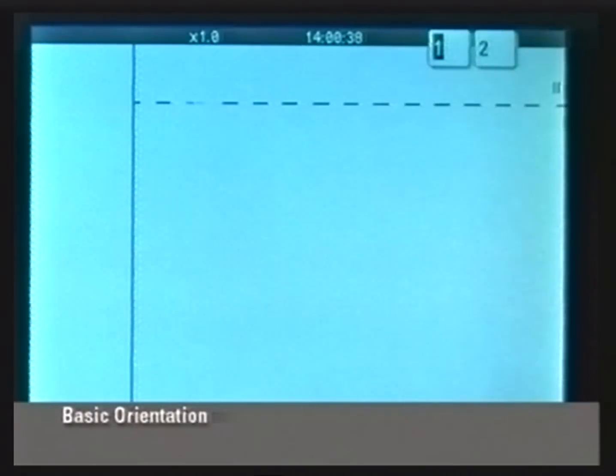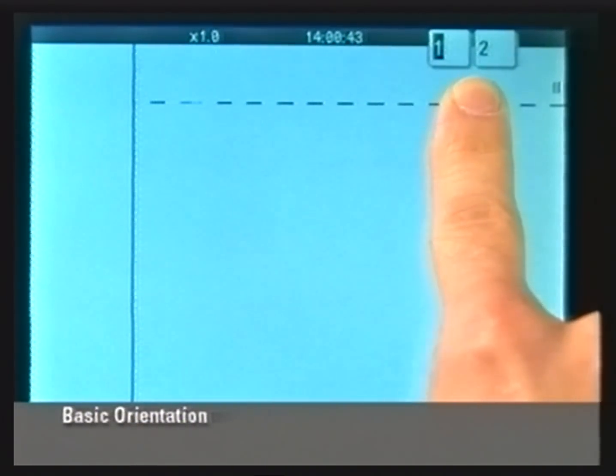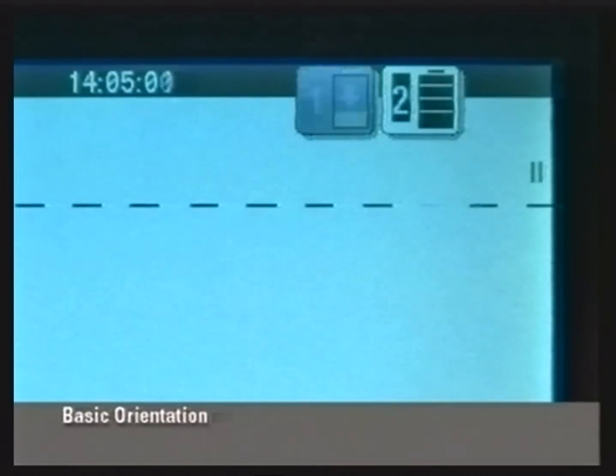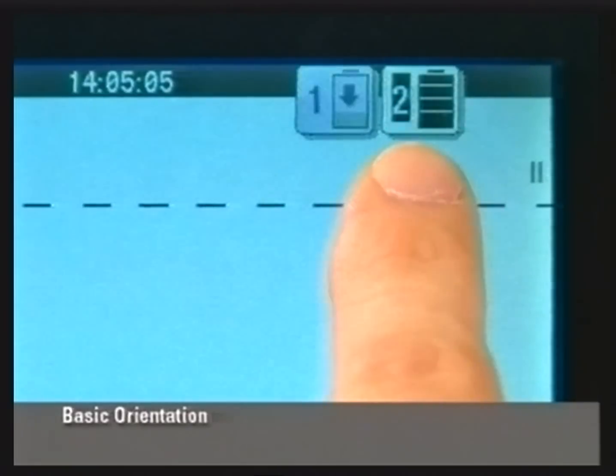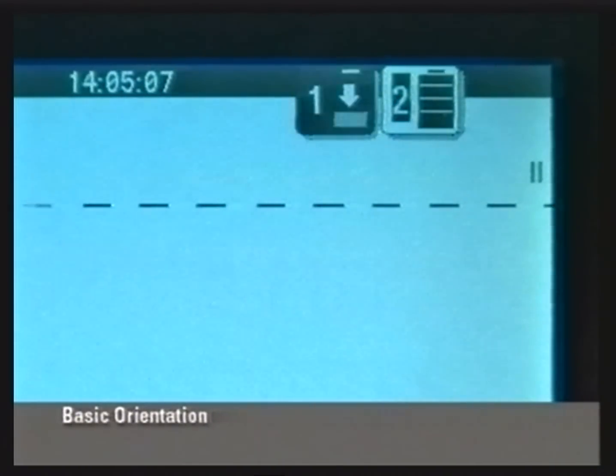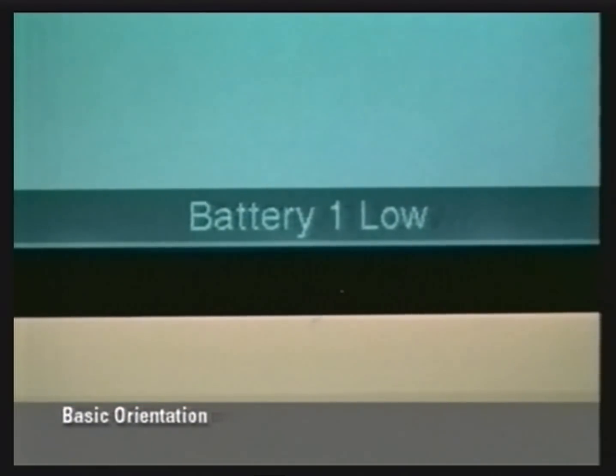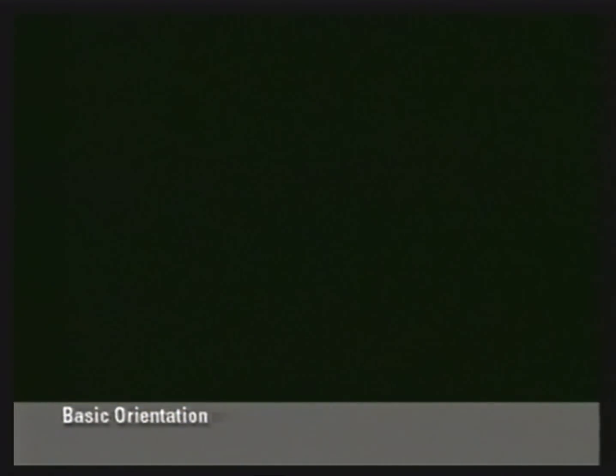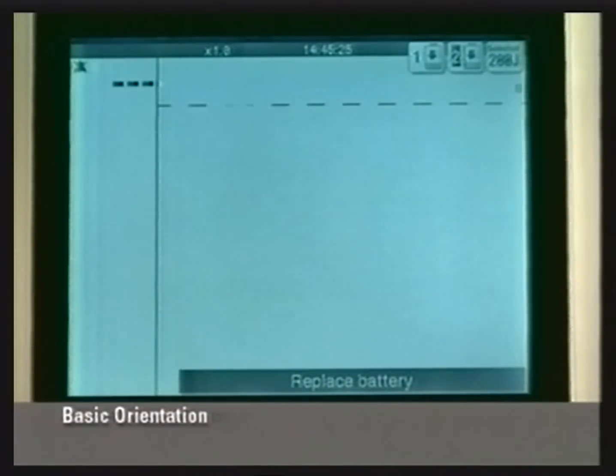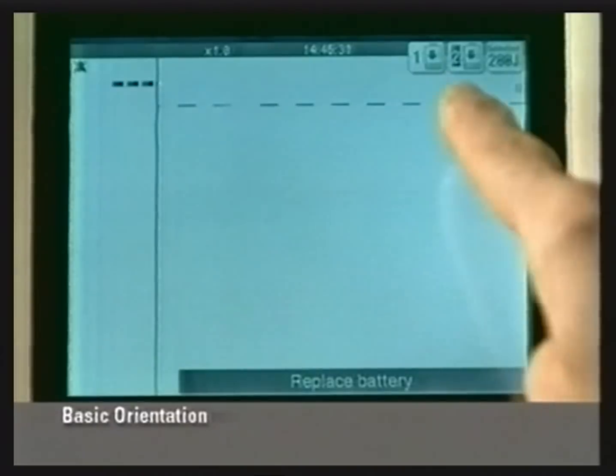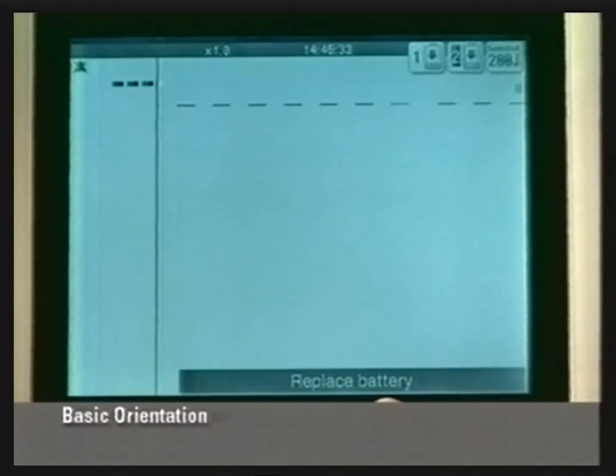Charge status for Fastpack batteries 1 and 2 is indicated by battery symbols on the screen. Because the Lifepak batteries communicate with the monitor, the battery symbol shows the level of charge. A low battery is indicated by this symbol. A battery low message with a tone indicates when one battery is low. The replace battery message along with a tone or voice prompt indicates both batteries are low. Replace one or both batteries immediately to prevent shutdown of the defibrillator.